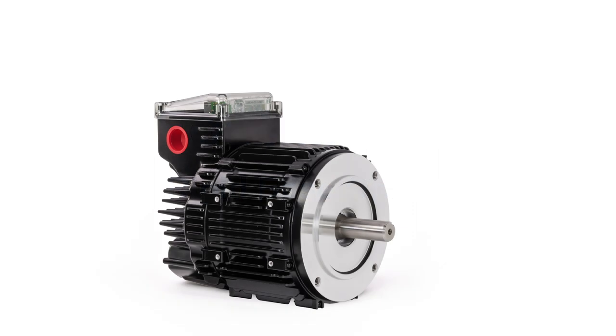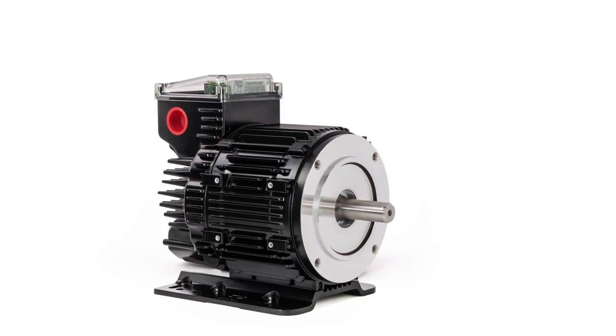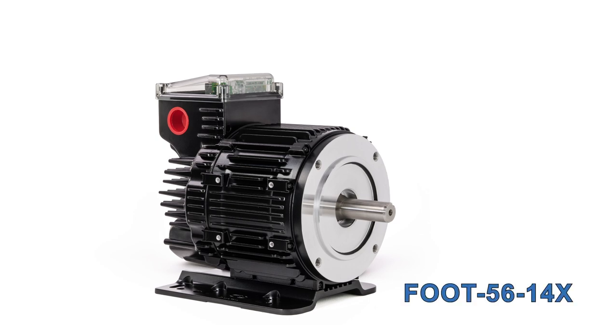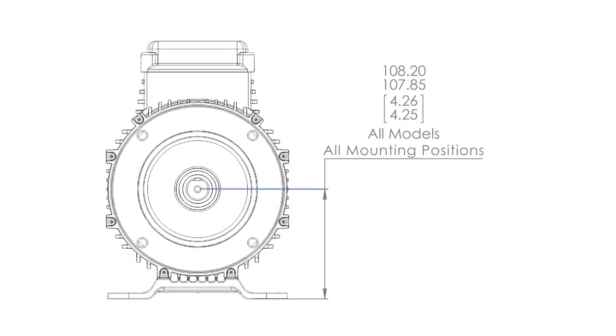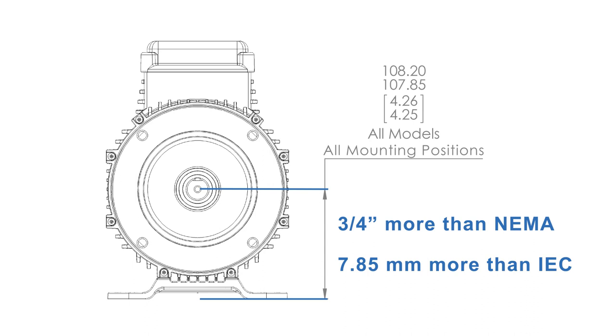In addition to standard face mounting, ClearPath integral horsepower motors can be foot mounted using the cast aluminum rigid base foot mount accessory. The foot can be attached to any of the three sides not occupied by the junction box. Be sure to note that the shaft center is 4.25 inches from the mounting surface of the foot — three-quarters of an inch more than the standard for NEMA 56 and NEMA 143 motors, and 7.85 millimeters more than the standard for IEC 100 frame size motors.